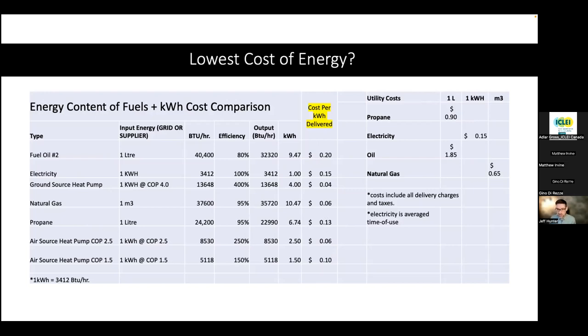Now, something that certainly has come into the marketplace over the last decade is air source heat pumps and cold climate air source heat pumps. And how do they fit into this conversation? I've positioned them with two data points here, because often consumers in rural areas are going to see information about ground source heat pumps and cold climate air source heat pumps that rate them at this performance level. And I've shown 2.5 here, because there's marketing from manufacturers on equipment, and then there's what actually happens in the field. Now, 2.5, we're talking about 250% efficient. So we put 1 kilowatt hour into it, we get 2.5 kilowatt hours out of it. Those are in pretty typical conditions, but we also see conditions that are peak. So in those not so good situations that happen every year, those colder situations, or even in those ultra warm situations, the performance of air source equipment is going to suffer because we're using that air as that heat exchange medium.